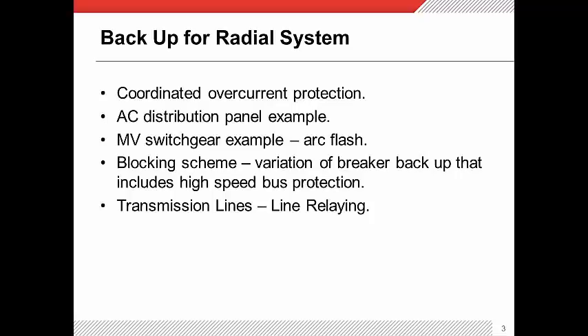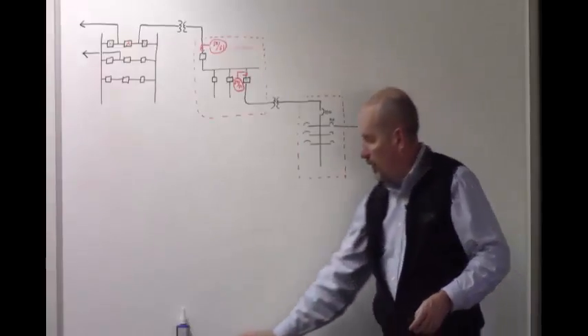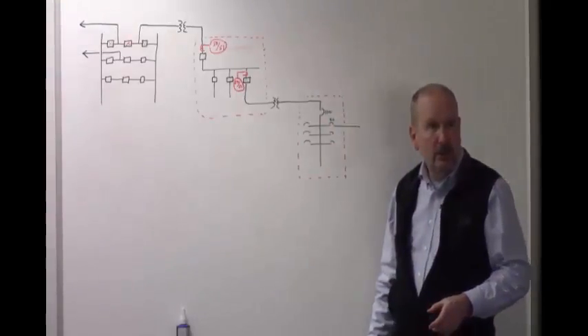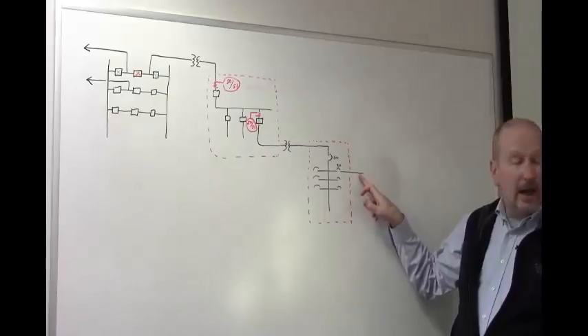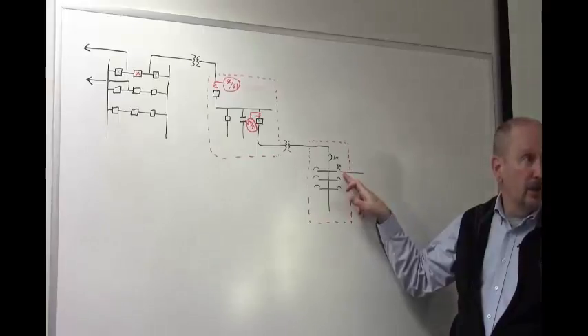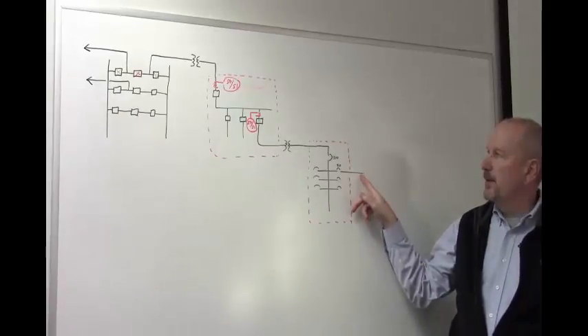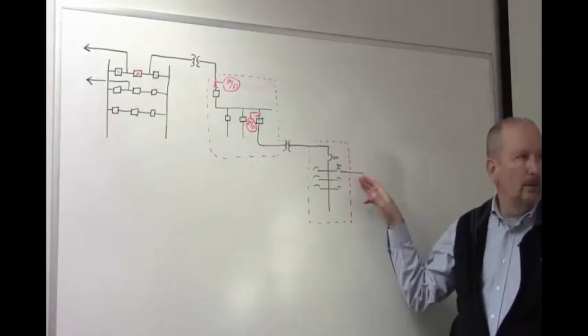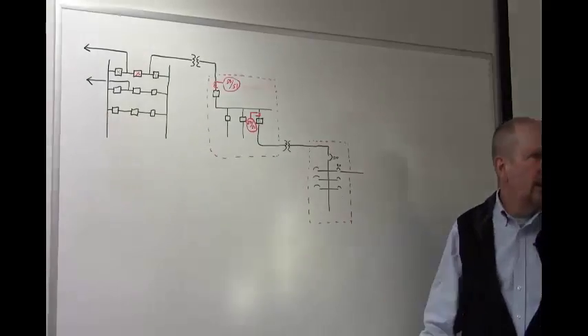Looking at what I've drawn on the whiteboard: I've got a system we might find in a substation, drawn all the way down in voltage to the AC panel providing station service. I've got a 100-amp main breaker. If we have a fault on a feeder and a 20-amp breaker fails to clear it, the main will open — there's enough fault current to operate the main breaker, which picks that up. Pretty straightforward.